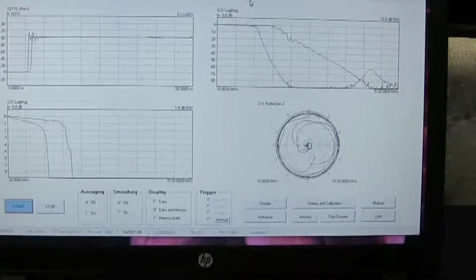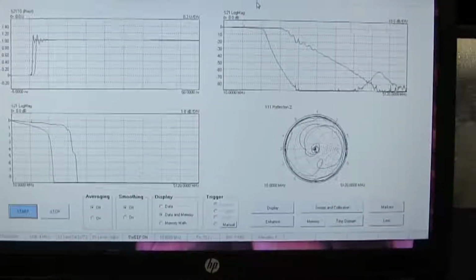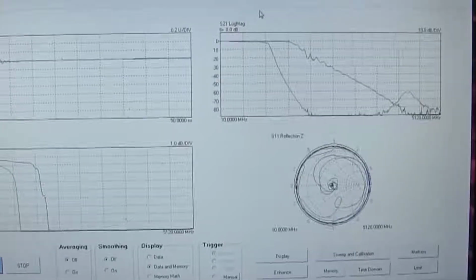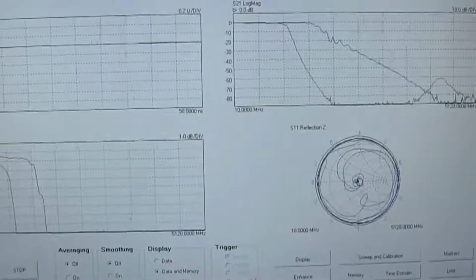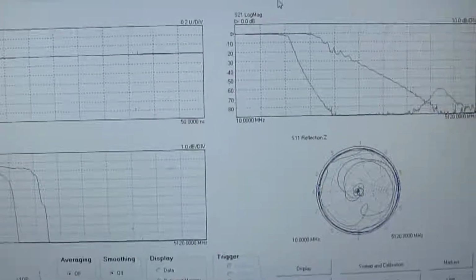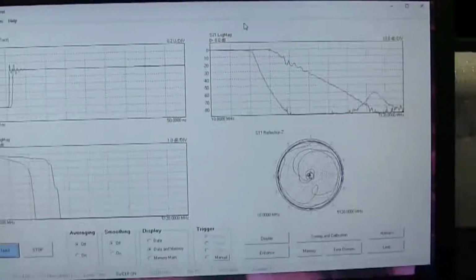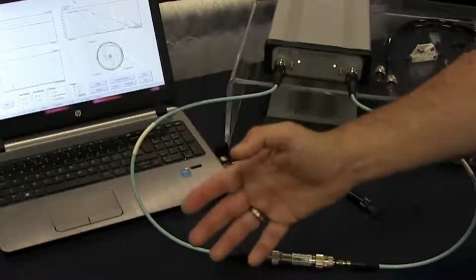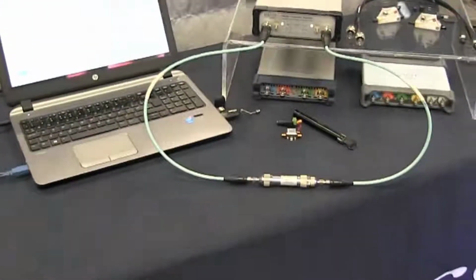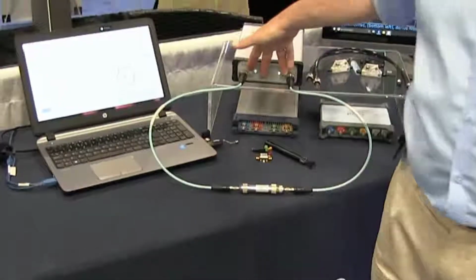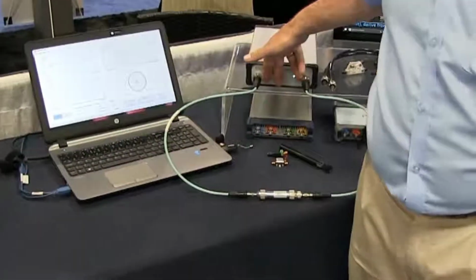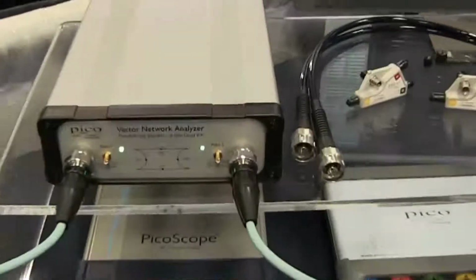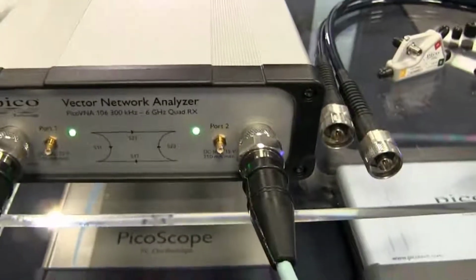All of the normal plots that you would expect to be available, the plot formats for all of the 4 S-parameters are available through the software. We've already mentioned that it has time domain included for that price that we've just seen, just a tad less than $6,000. Time domain not an option that you have to pay for. Notice also that the product has bias tees on both ports. Again, an option that you do not have to pay any further for.